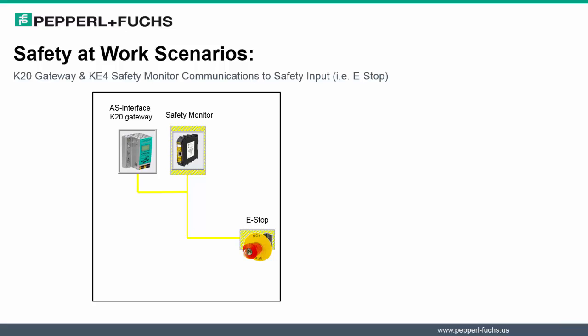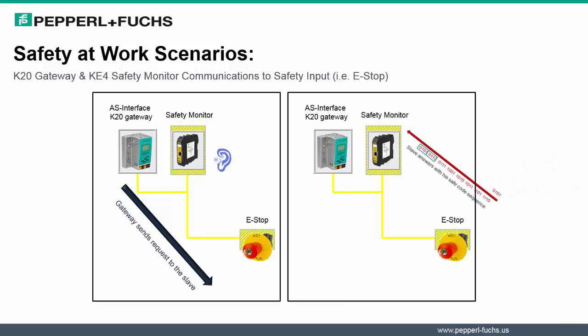Now let's discuss how the prior scenario changes when the K20 gateway works as a separate unit from the safety monitor. As with the prior scenario, the gateway still initiates or sends the request to the slave. However, instead of the gateway listening back for the response, the safety monitor, the separate unit, is listening for the response back in this scenario. The slave again responds back with its safe code sequence. Once the safe code sequence has been transmitted from the module to the AS Interface gateway, special rules are used by the safety monitor to determine whether the e-stop has been activated.